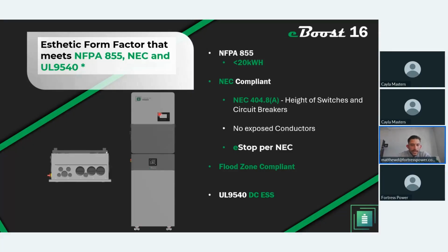Now, as I mentioned before, this battery will certainly meet a lot of the NEC codes and UL standards. It will meet NFPA as it's below the 20 kilowatt-hour capacity per unit. It won't have any exposed conductors, right? Because we made the wireway with side knockouts, so you can run wires from one side to the other through conduit and create safety within the premises.